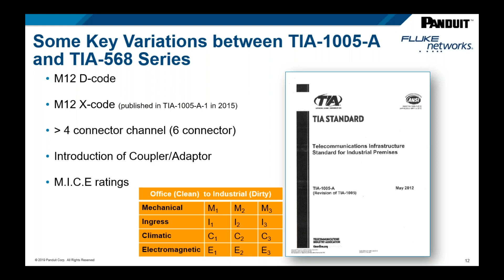Recognizing that architectural difference, the standard also accommodates the nature of industrial deployment, such as systems in control panels, adjusting for those MICE criteria. With TIA 1005A, you have M12 connectors recognized in both D-code and X-code formats, six-connector channels are possible and recognized, which can happen running in and out of control panels where you need to seal the connection, so you may end up with more connectors following this strategy. Finally, the use of couplers and adapters is also recognized in 1005A.